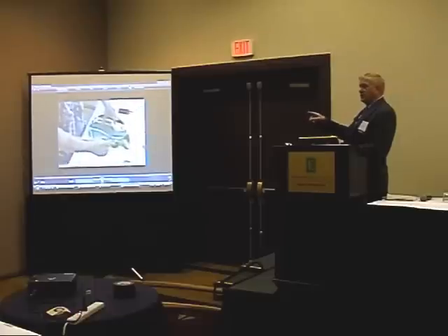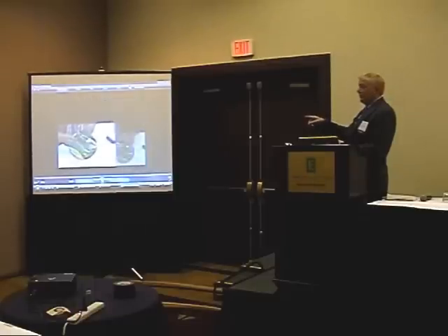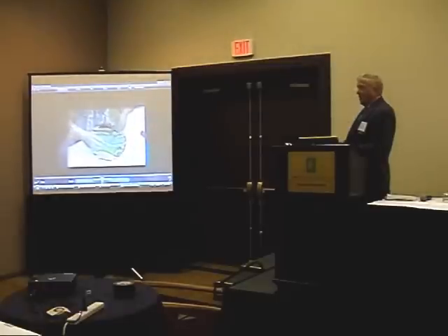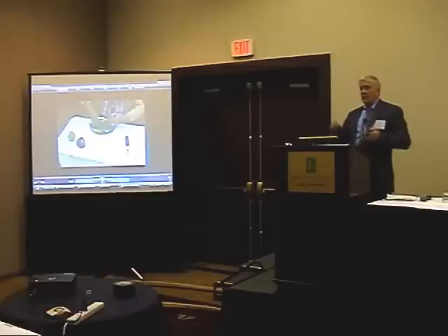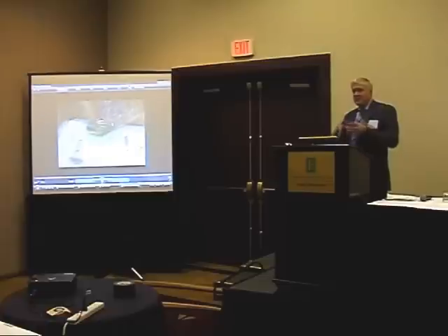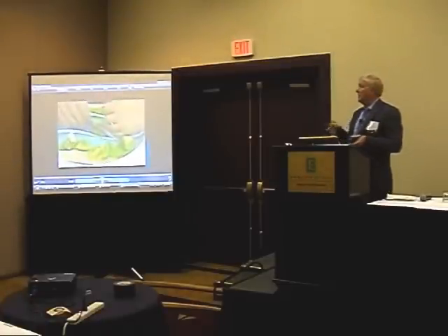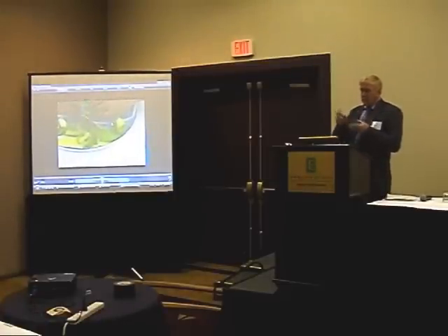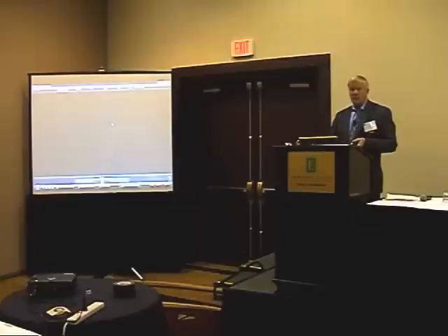Believe it or not, these are suction sockets. So how do we handle that? Well, the easiest way to handle the suction socket is with a straw. If you have the arm sockets there, and they're designed as suction sockets, and you're using suction electrodes, because Ottobock makes those suction electrodes that are flush, if you moisten the arm and you put a straw in the socket, you can push directly down, the air will evacuate, you can pull that straw out, and now it's strictly suction. And it works every time. Straightforward, intuitive, easy to use.